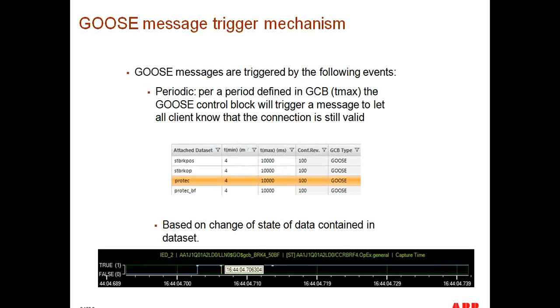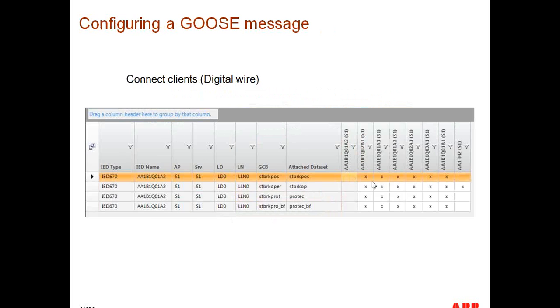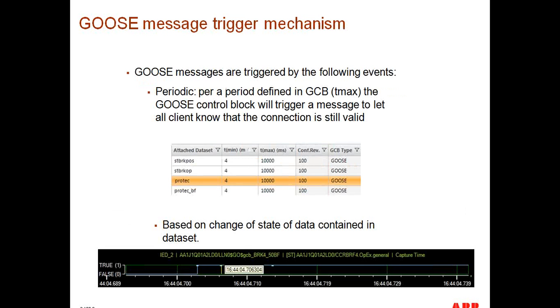Now, the trigger mechanism of Goose messages. Goose messages are triggered by the following events. Periodic, which means that we send a heartbeat message to make sure that the connection between the device that's supposed to send and the device that's supposed to receive this information is in good standing. The period of this message is defined by Tmax in your Goose control block. In this case, this is set to 10,000 milliseconds, or 10 seconds. So every 10 seconds, the devices connected to that message will expect a message from the device that's publishing this information. If they do not receive it after 10 seconds, then they can trigger an alarm and inform that the connection is broken. That's the mechanism that allows Goose messages to be self-monitoring connections.